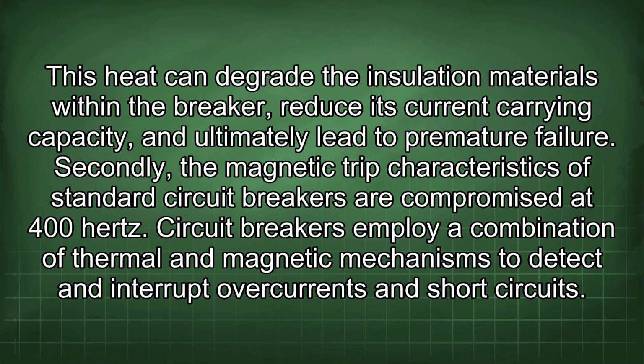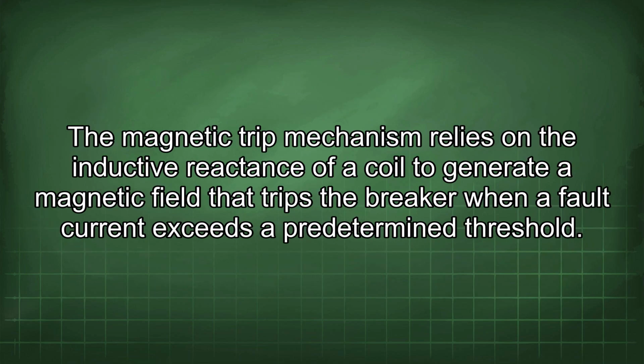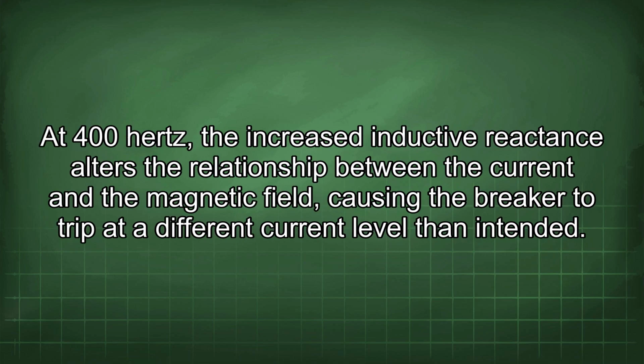Circuit breakers employ a combination of thermal and magnetic mechanisms to detect and interrupt overcurrents and short circuits. The magnetic trip mechanism relies on the inductive reactance of a coil to generate a magnetic field that trips the breaker when a fault current exceeds a predetermined threshold. At 400 Hz, the increased inductive reactance alters the relationship between the current and the magnetic field, causing the breaker to trip at a different current level than intended.